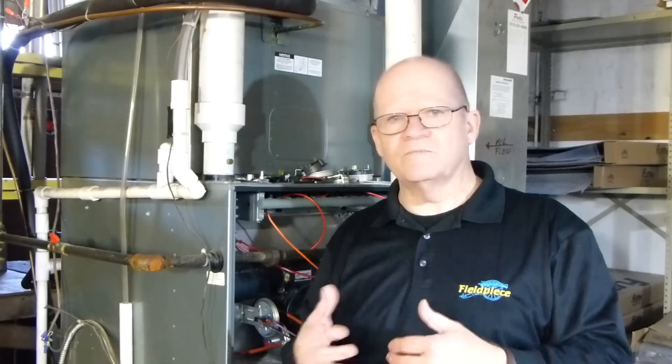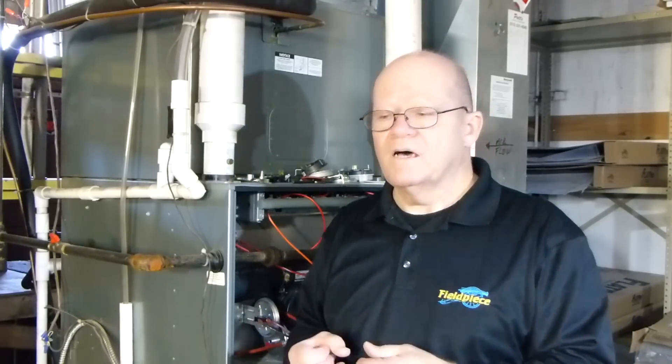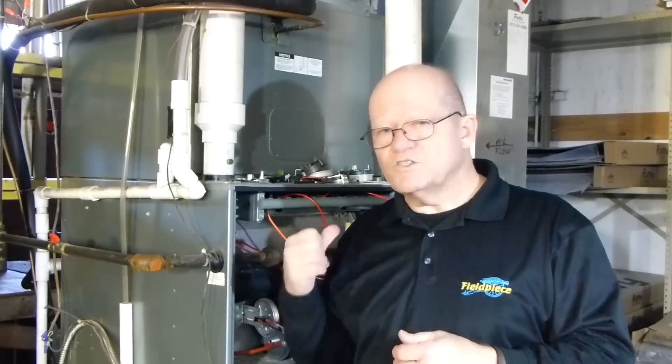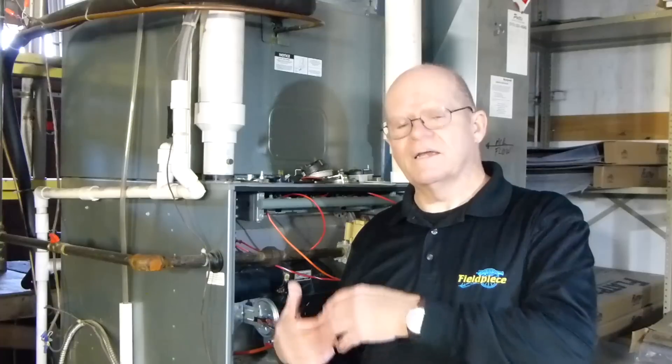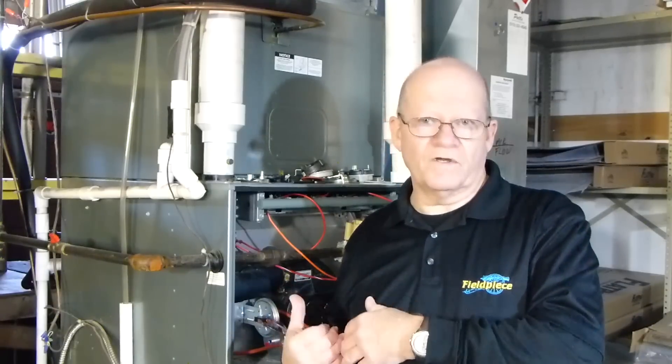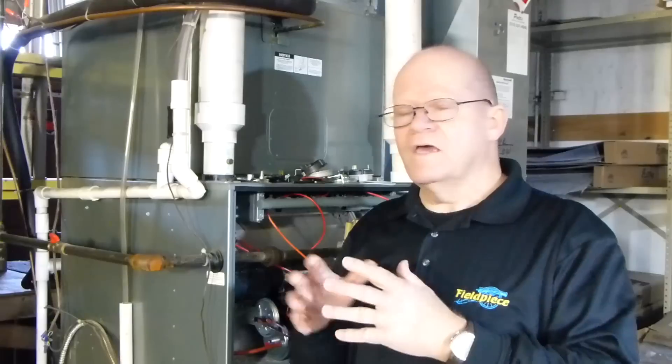So a lot of them are designed without a bleed port. Make sure that it is specifically designed for the furnace and it's UL approved. I would highly recommend that. There are some that do not have bleed ports on them that are in furnaces as well, so pay attention to that. And for the most part, those are just trying to prove whether or not there is any draft at all.